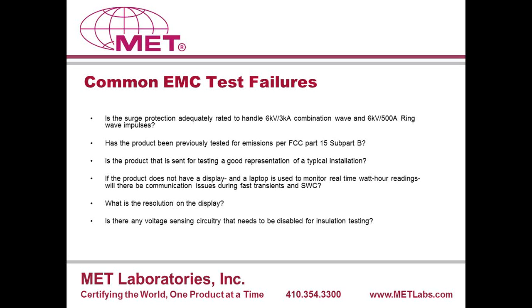We start off with series testing. We go through insulation test, voltage interruptions, and a surge test. Mostly the combination wave test is when we see a failure, where we would see some of the fuses open, we would see the display go out. So those are some of the things that we would see mostly on a combination wave surge test.